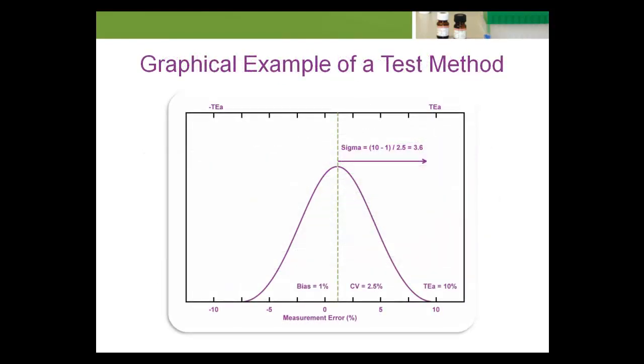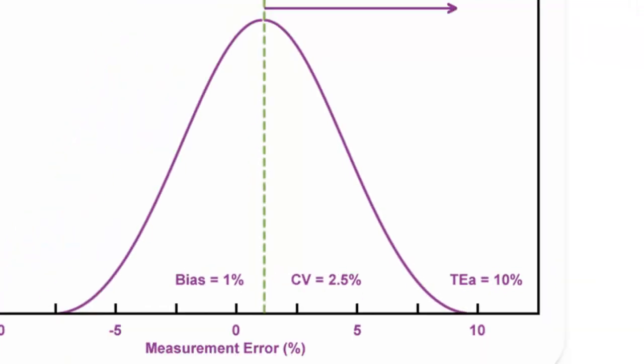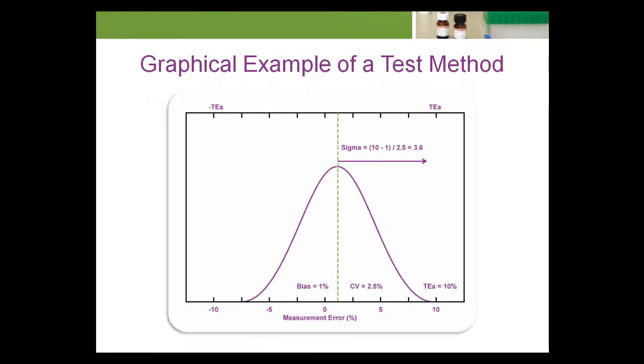The chart shows a graphical example of a test method with one percent bias, 2.5 percent coefficient of variation, and a specified allowable total error of 10 percent. In this case, the sigma value is 10 minus 1 divided by 2.5 equals 3.6. That is, 3.6 analytical SDs fit within the 10 percent quality specification.